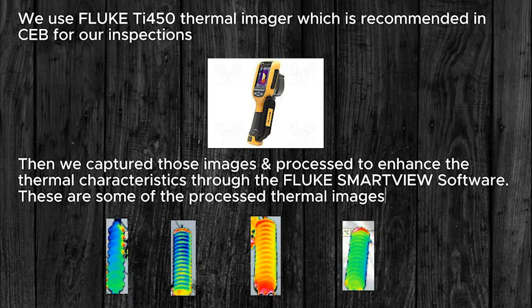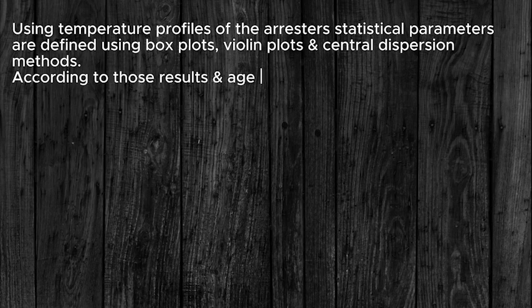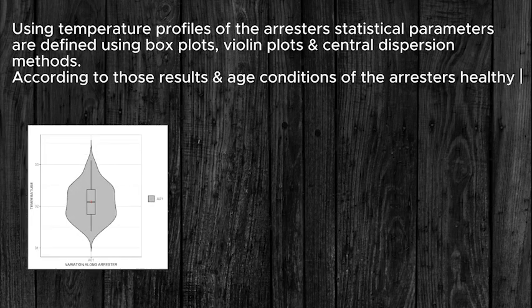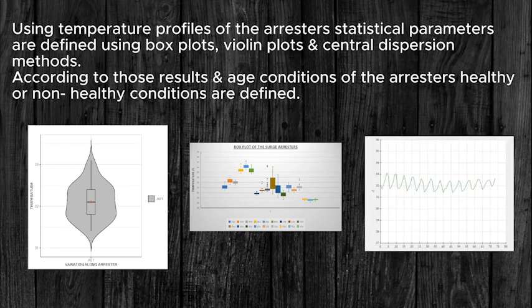These are some of the processed thermal images. Using temperature profiles of the arresters, statistical parameters are defined using box plots, violin plots, and central dispersion methods. According to those results, the healthy or non-healthy conditions of the arresters are defined.